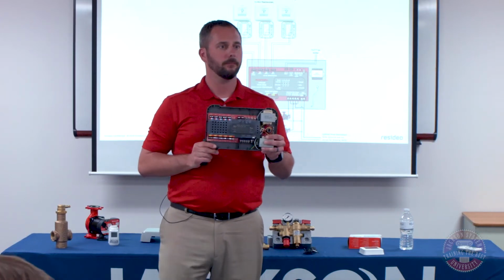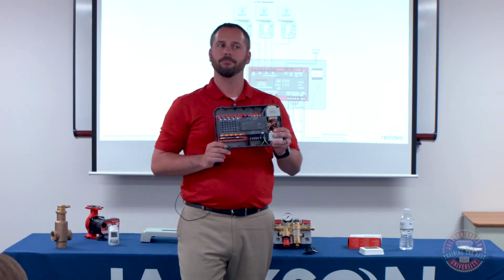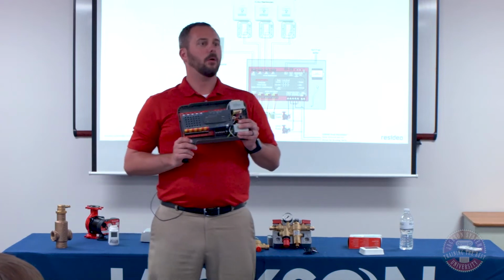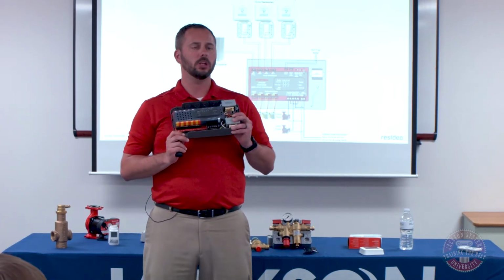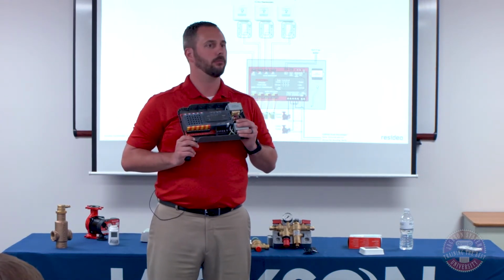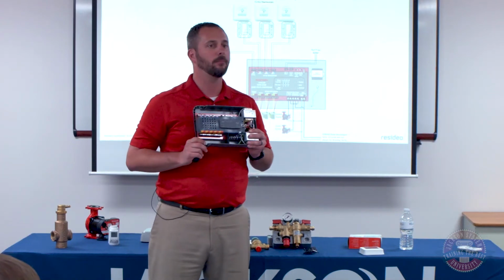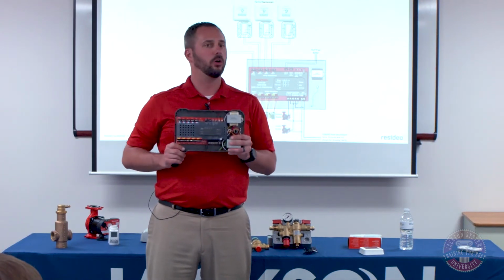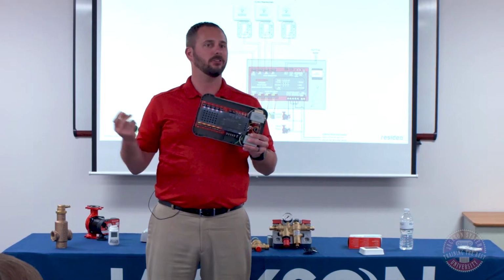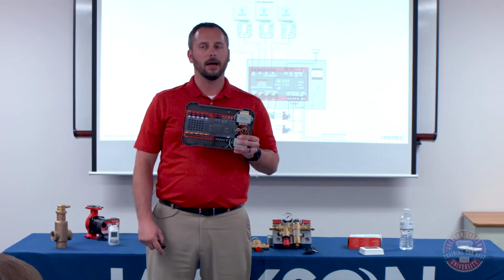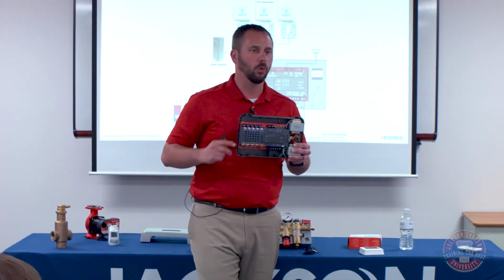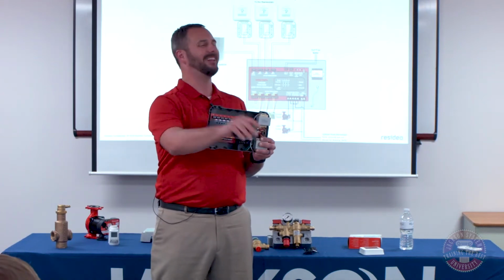Another quick question, no shielded cable needed. Nope. Just regular thermostat wire. Regular thermostat wire is fine. Shielded cable is typically used when you have resistors, so sensors are kind of what drive that. With this, all we're doing is opening and closing relays, so it just needs kind of an on-off call. So yeah, shielded wire doesn't hurt. It works fine, it's not needed.